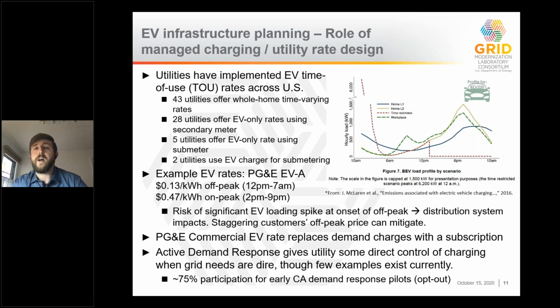Things to consider: what are you applying that EV-specific time of use rate to? Is it to the whole home? EVs are the largest single appliance a homeowner would have, so engagement in time of use through an EV can have impacts, especially if on the same schedule, on the rest of the house load. Or is this time of use rate applying to the EV only, in which case you need a sub-meter or secondary meter? In some cases utilities have chosen to allow the native metering infrastructure already built into most charging stations to provide that sub-metering to the utility.